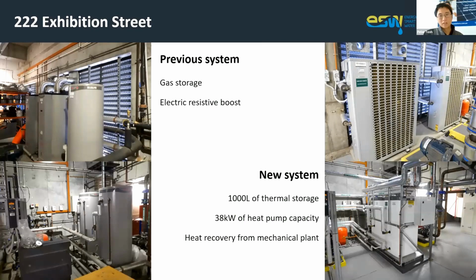Hi, thank you, Shane. This is another project in the Melbourne CBD, Triple Two Exhibition Street. As you can see, the previous system is a combination of a gas storage and electric resistive system. We replaced that with 2 tanks and 2 of the 19 kilowatt heat pumps. So in this case, 1,000 liter storage and 38 kilowatt of heat pump capacity. The uniqueness of this project is that we're also taking heat recovery from a mechanical plant to offset the heat pump runtime.